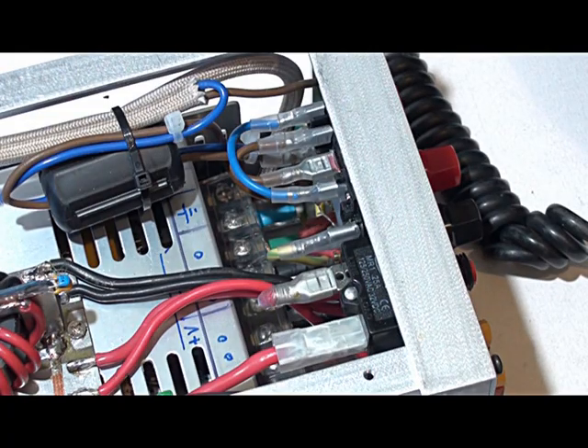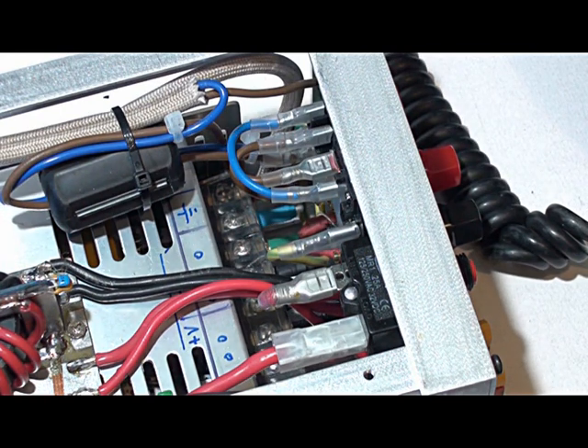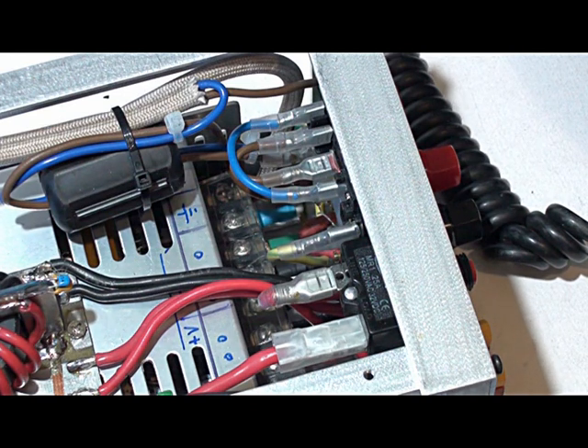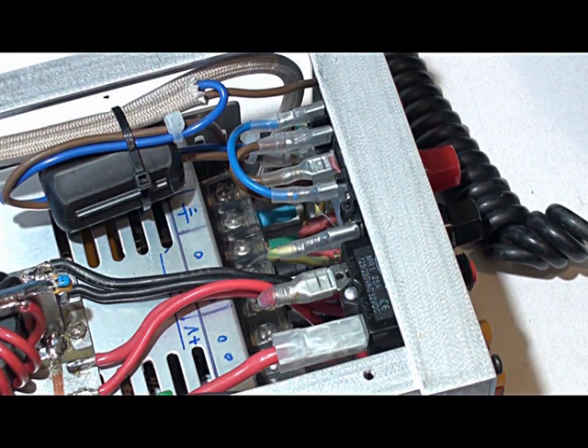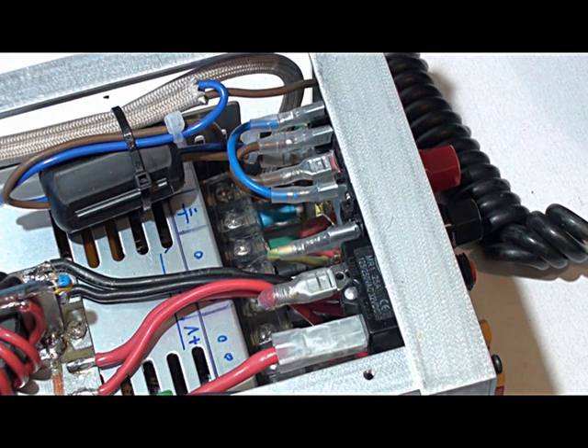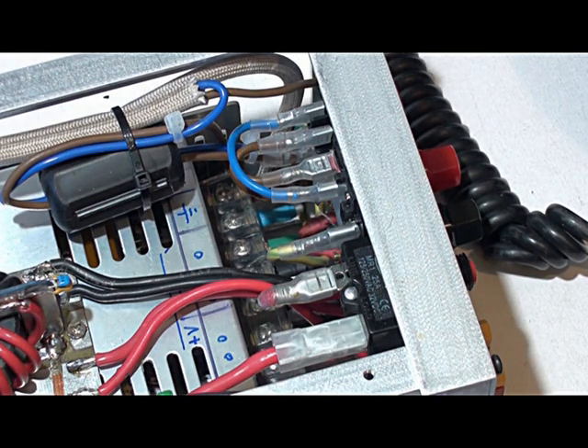This is a closer view of the back panel showing the clip-on leads, the glide-ons. Right in the far corner there's an earth bolt consisting of a bolt with two interlocking nuts, and the earth from the IEC connector and the earth to the power supply both go to that one spot.